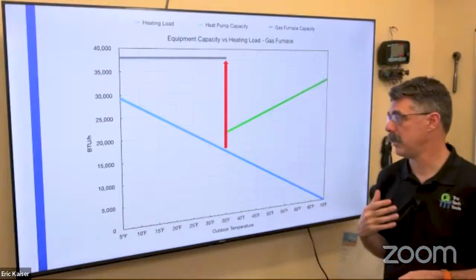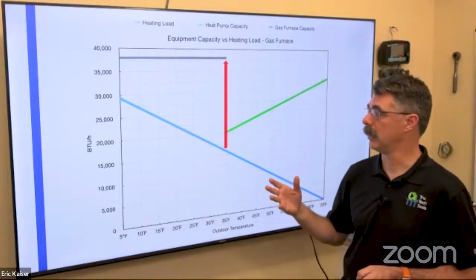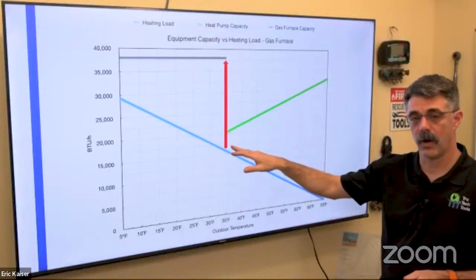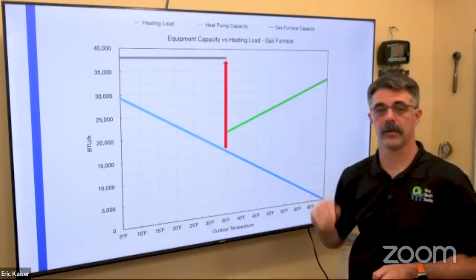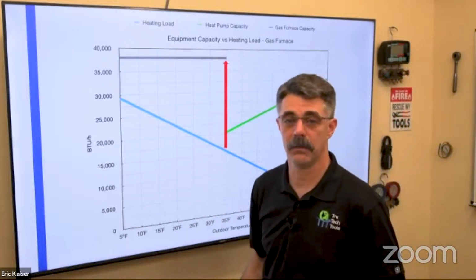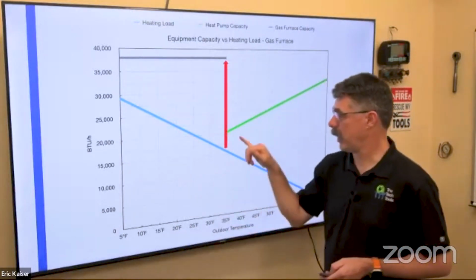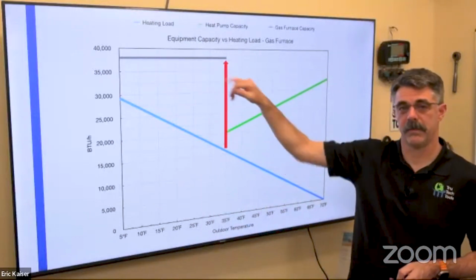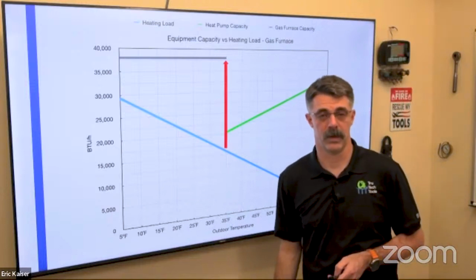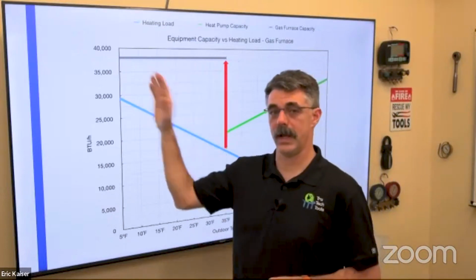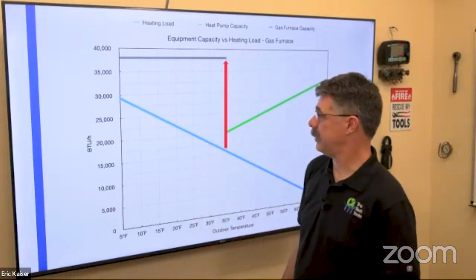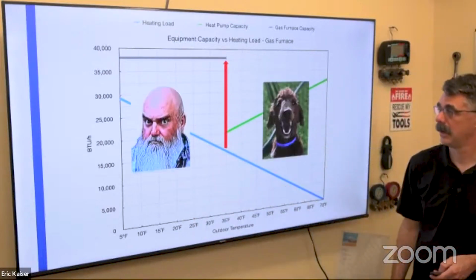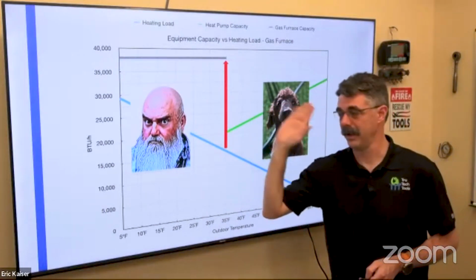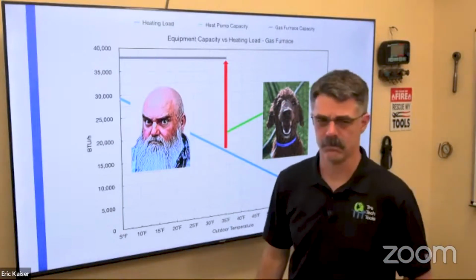And this is actually something that happened to me personally in my house one time where I had a dual fuel. Anytime my heat pump would turn off, right, and my gas furnace would come on, I would be uncomfortable in the house because my runtime went from almost 100% to maybe 50%. Maybe it was 60% runtime until my temperature went way down here. So my comfort level decreased a lot, right? And then there was this, and we kind of had that dividing line. Oh, I'm nice and happy and comfortable. Hit that line. Angry Ed's over there staring at me like, what did you do? And why am I not comfortable?